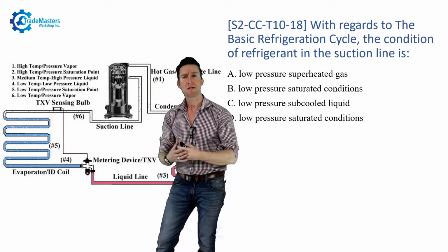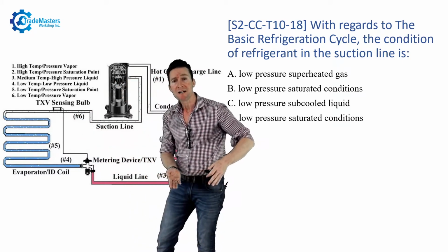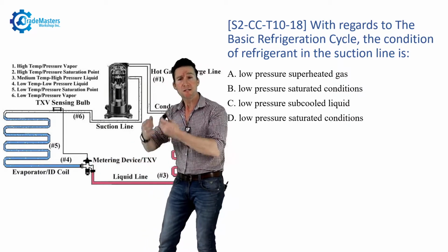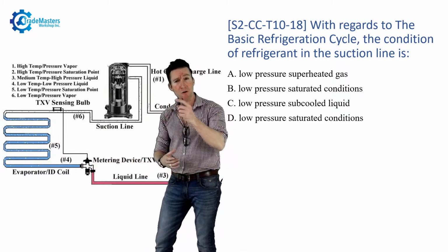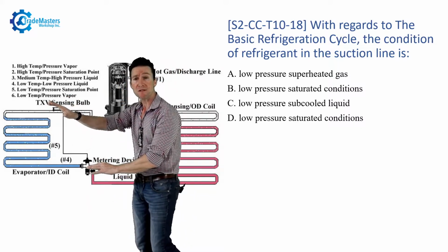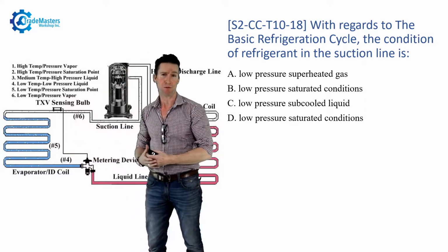The reason the refrigerant in the evaporator is experiencing low pressure is because liquid fed from the liquid line through a restrictive metering device causes a sudden pressure and corresponding temperature drop, which creates the low side pressure of the system and establishes the beginning of the boiling process in the evaporator.